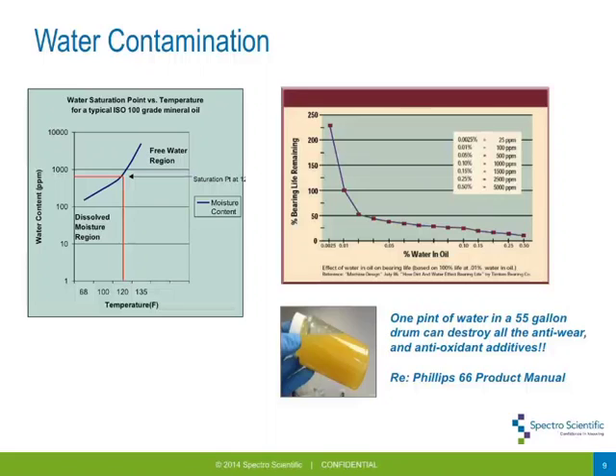Many bearing companies and equipment manufacturers all tell you to keep water out and under control. Even water getting into a brand new drum of oil can have serious side effects — water can react with and destroy additives before you have a chance to use the oil. Phillips 66 makes it quite clear in their product manual: keep the water out of the system because it will destroy the additives. So if you see a watery oil, you definitely want to do something about it before putting it into a system — preferably feed and bleed it.